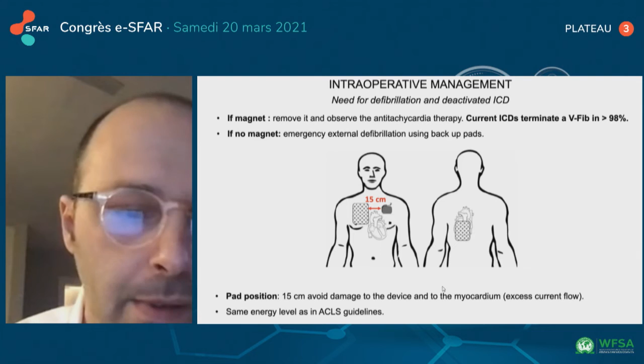The better pad position, which should be put in place before anesthesia induction, is the anterior-posterior pad position. Please try to respect a 15 centimeter distance between the pad and the generator, because you can induce a problem in the device and in the myocardium if you shock directly over the device. Please also use the same energy levels as you would according to the guidelines.